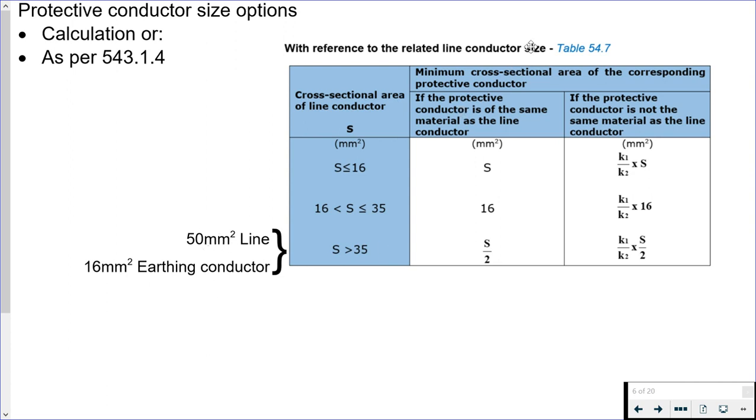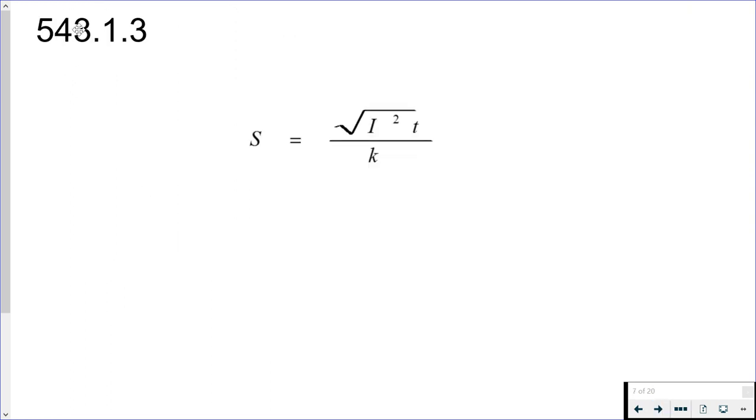If we were selecting as per regulation 543.1.4, then that protective conductor would have to be at least 25 millimeter squared. So the protective conductor has not been selected as per the second point. Hopefully if this is an initial verification you'll have the calculations there from the designer, but if it's a periodic inspection you probably will not, so you'll have to carry out the calculation yourself to confirm that this 16 millimeter squared earthing conductor meets the requirements for thermal constraints. 543.1.3, that's where we have the calculation method.